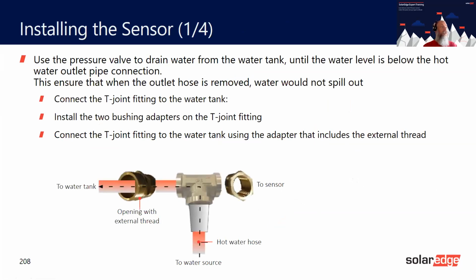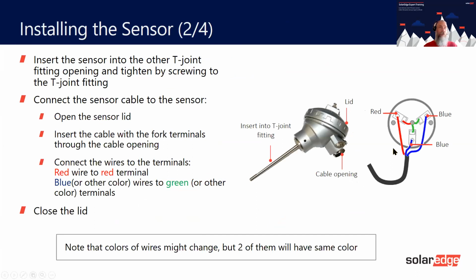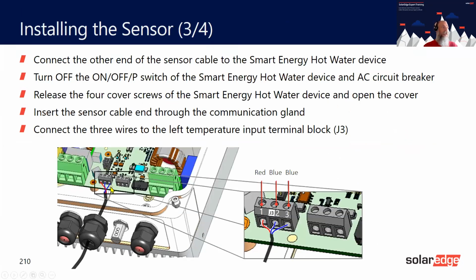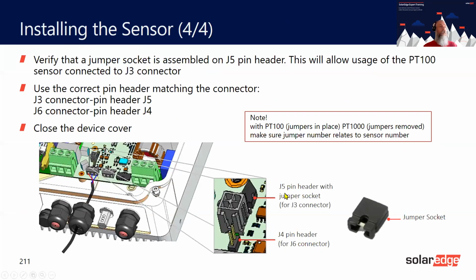I just want to show you a couple of pictures here of how it would connect. You have two cables, the same, two blues and a red, and these are all done on the inverter very simply in here. So this is the bit on here. You simply put the two colors that are there together in this terminal, into 2 and the 3, and then that's it. Very simple. You don't need to remove any of the jumpers. So these are the tiny little bits here. You don't need to remove any of those with a PT100. So please make sure you're using a PT100. And that is pretty much it for me.